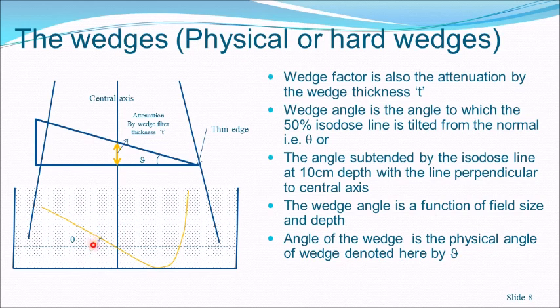If this angle is 15 degrees, the wedge is called a 15-degree wedge; if 30, a 30-degree wedge. The attenuation by the wedge at the central axis is referred to as the wedge factor, discussed in detail previously. The wedge angle is a function of field size and depth, but the reference wedge angle is taken at either the 50% isodose line or the isodose line at 10 cm depth.